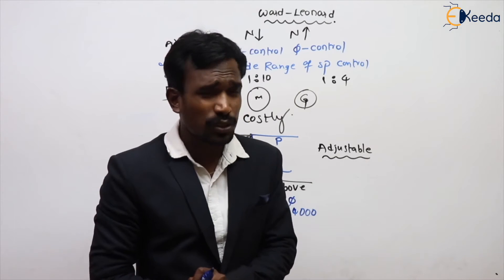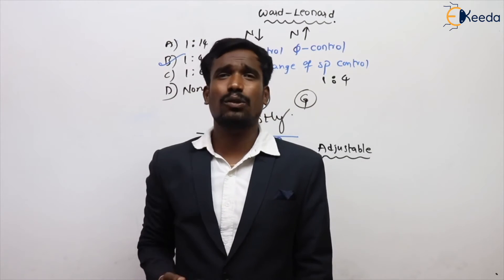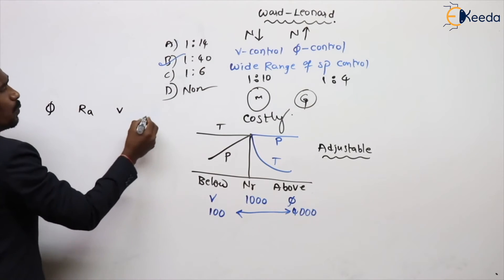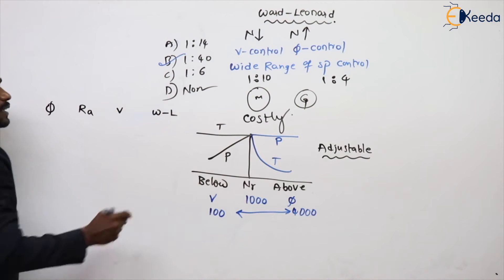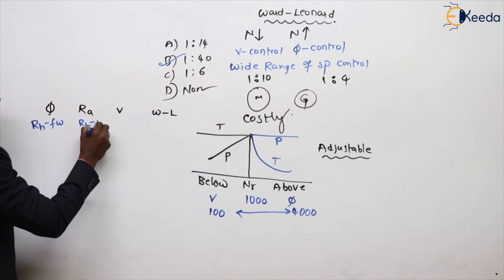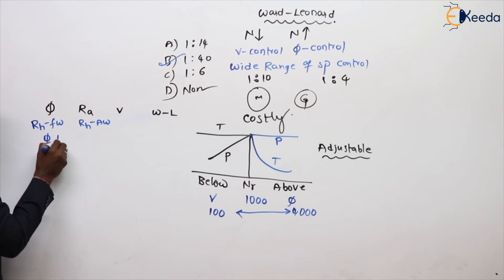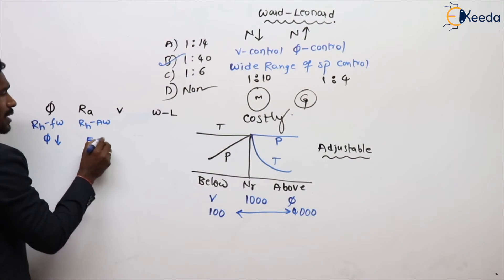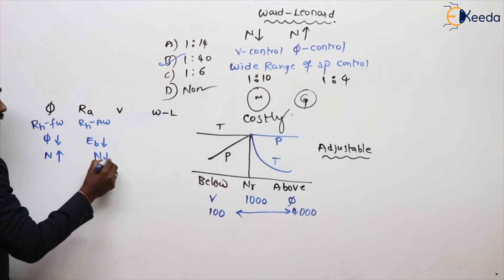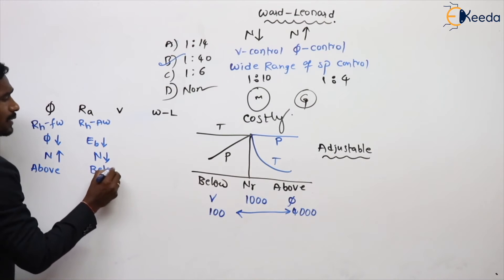So like this, the speed control methods in our DC machine are: flux control method — extra rheostat added in the field winding; armature resistance control method — extra rheostat added in the armature winding; voltage control method; and Ward-Leonard speed control method. In flux control, when resistance increases, flux reduces, so speed increases. In armature resistance control, when resistance increases, Eb reduces, so speed decreases. Flux control is only for above rated speed; armature resistance control is only for below rated speed.